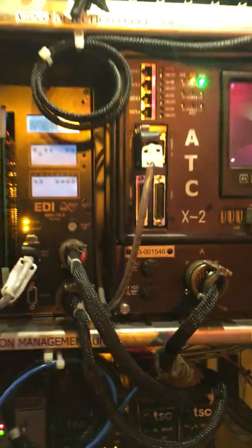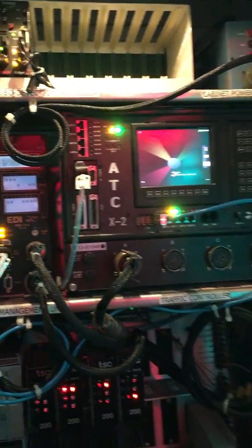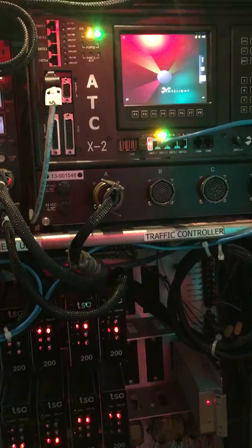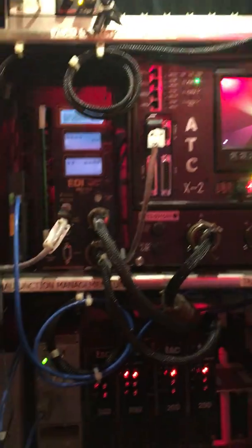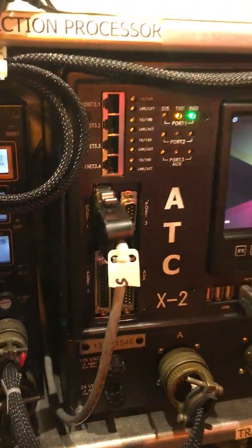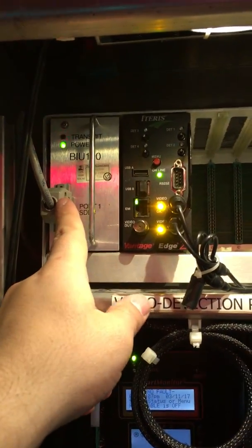This particular cabinet is a TS2 Type 1. There are three different configurations of a NEMA TS cabinet. There's TS1, which is the older version that used ABC ports with a direct wire for each component. TS2 eliminated that by including a serial bus so that everything talks to each other. That's what this cable is — it's called an SDLC cable, or synchronous data-link control, so the controller talks to the malfunction unit as well as the detector rack through this communication bus interface unit.